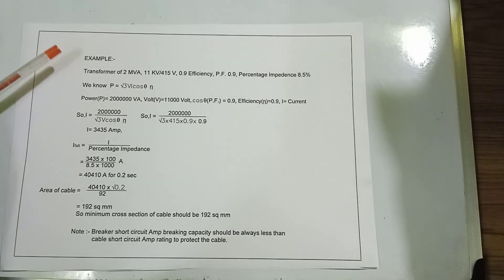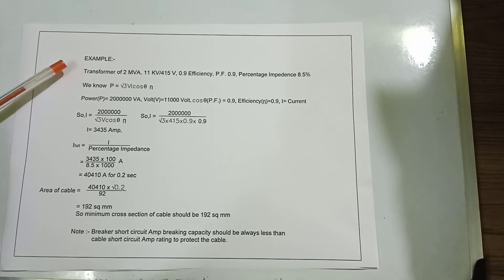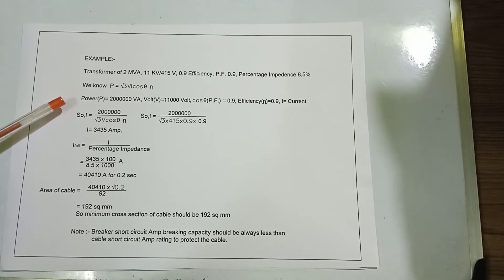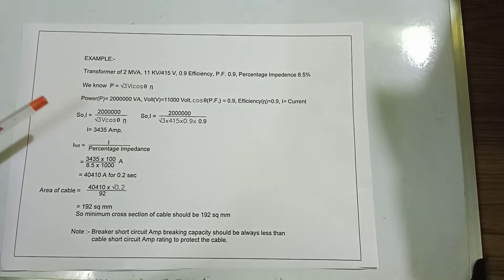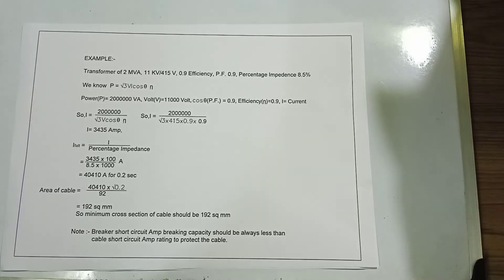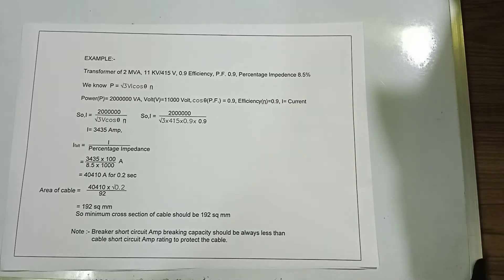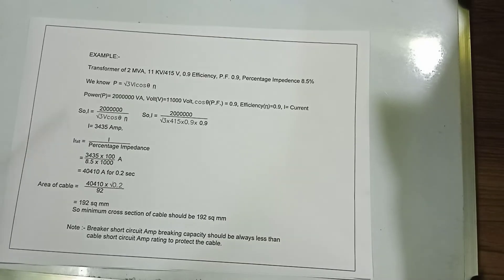Here is an example: a transformer of 2 MVA, 11 kV by 415 volt, efficiency 0.9, power factor 0.9, and percentage impedance 8.5%. We use the formula P = √3 × V × I × cos θ × efficiency.